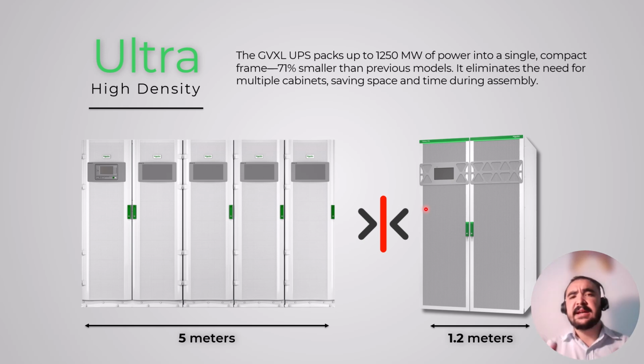What happens is, with the Galaxy VX, the UPS would come as a standalone unit, with no built-in batteries or power modules to support its power needs. You would need 5 I/O cabinets, 5 of these, 1, 2, 3, 4, and 5. Each of these cabinets is rated at 250 kilowatt of power and attached to the UPS in order for it to provide the 1.25 megawatt of power. What happened at the end? At the end of the setup, the total solution would span 5 meters in width, taking up nearly half of the room.